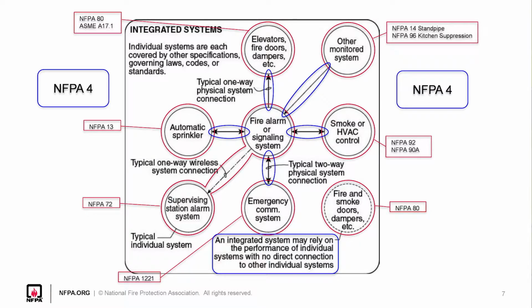And did it turn on within the right amount of time? I'm not making sure that the fan has the correct number of belts on it, or that the fan creates the right amount of CFM. I'm not looking at that stuff. I'm just making sure the fan turns on when specific devices tell the smoke control system to turn on. So another thing to talk about is NFPA 4 is covering those interconnections between those systems.